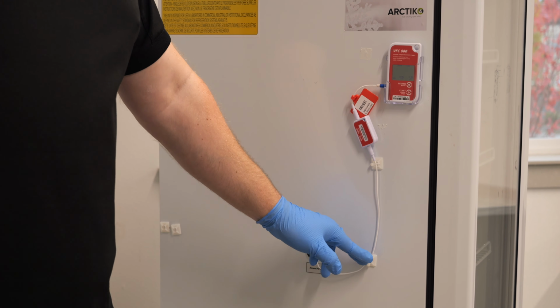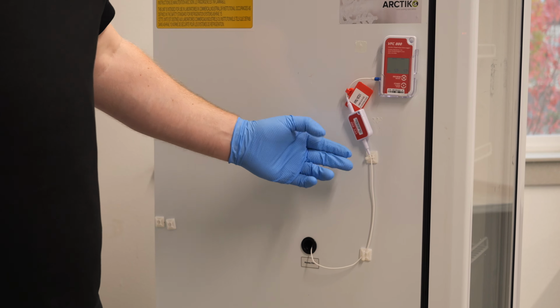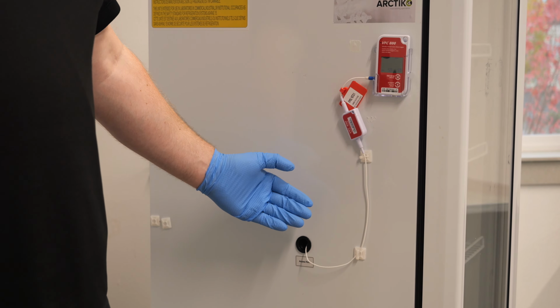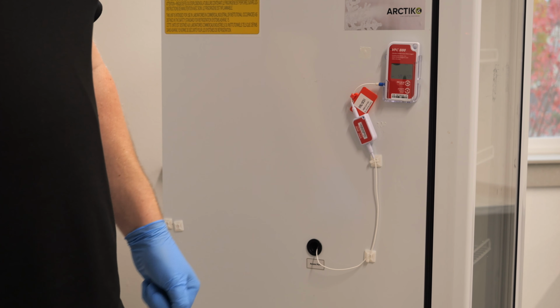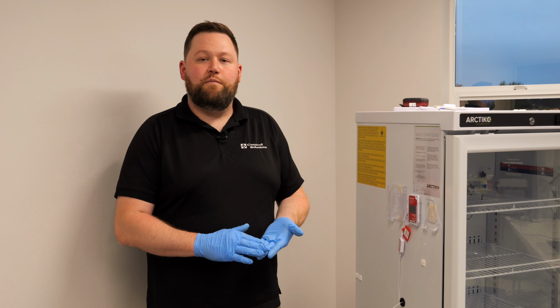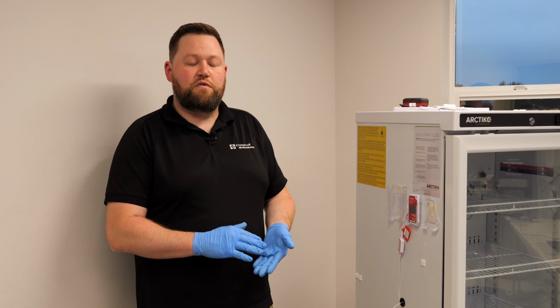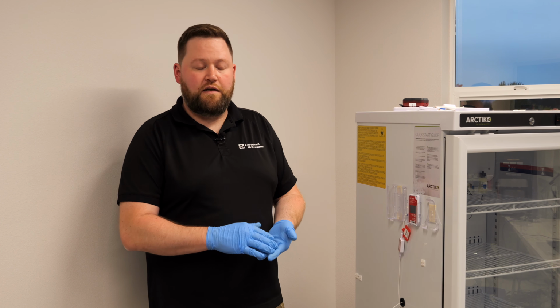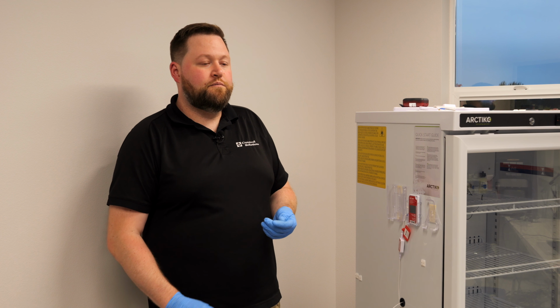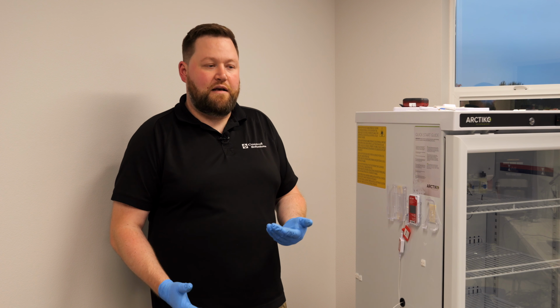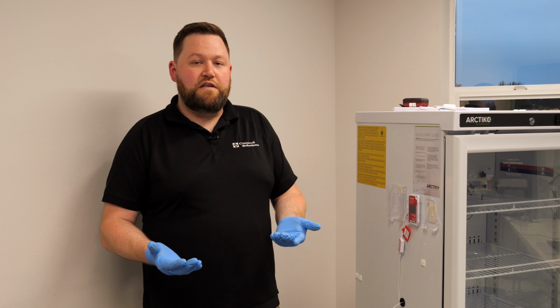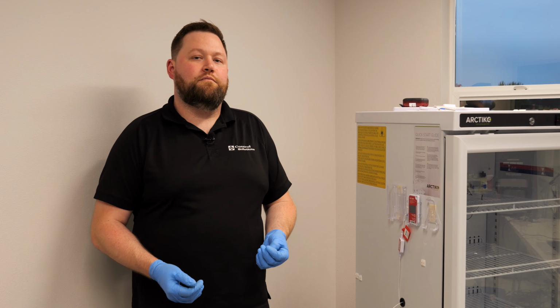After clipping off the excess from our cable ties, installation of our log tag temperature data logger is concluded. It has a user-resettable min and max temperature that you can reset daily if you would like to during your temperature audits. It also has a min and max temperature that is auto reset every night at midnight.